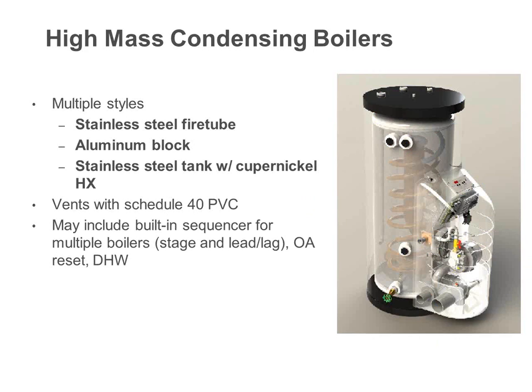Okay. This is sort of a residential version of a high mass condensing boiler. What this basically is, you think about it, we got a tank there, if you want to call it the buffer tank, with the heat exchanger inside, and what they actually do is just strap the boiler to the side of it, high efficiency boiler. Okay. It gives you all the benefits of the condensing boiler technology because it has a condensing boiler system on it. It also gives you the advantage of the high mass. So now if you have little zones firing on and off, it's not going to bother it because that burner is not going to kick on until you take the stored BTUs out of that tank.